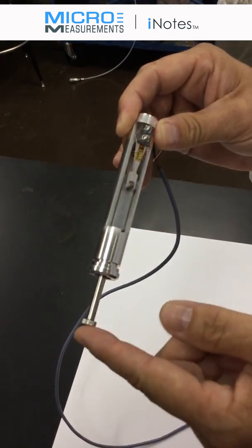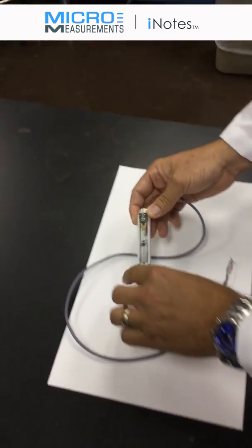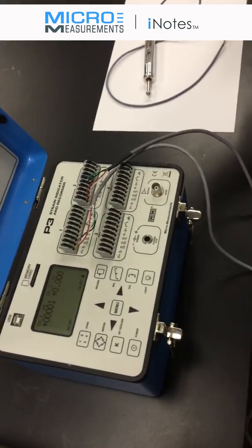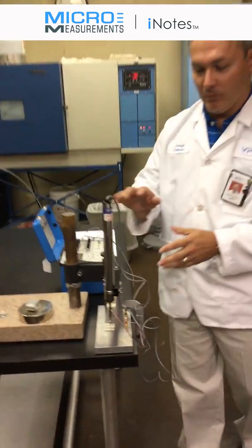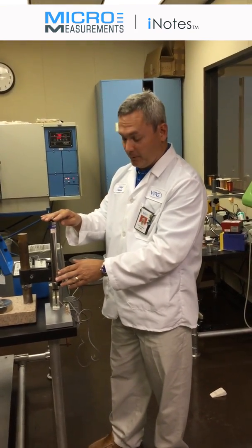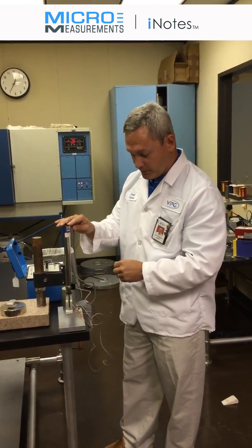We've got a full Wheatstone bridge inside of this, and that's what allows it to be connected to any strain gauge instrumentation. So let's take a look at our example. Again, we've got the HS100—that's 100 millimeter displacement, or basically four inches.